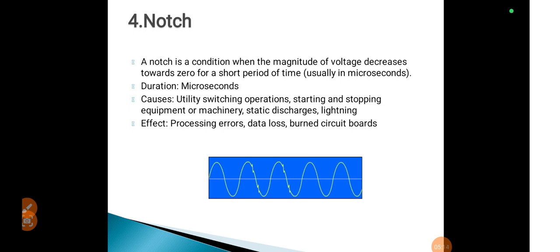The next power quality problem is notch. Notch is a condition when the magnitude of voltage decreases towards zero for a short period of time, usually in microseconds. Its duration is a few microseconds. Causes of notch are utility switching operations, the starting and stopping of equipment or machinery, static discharges and lightning. In these events, a notch can occur. The consequences of the notch are processing errors, data loss, or burning of circuit boards. The waveform for notch we can see in this diagram.